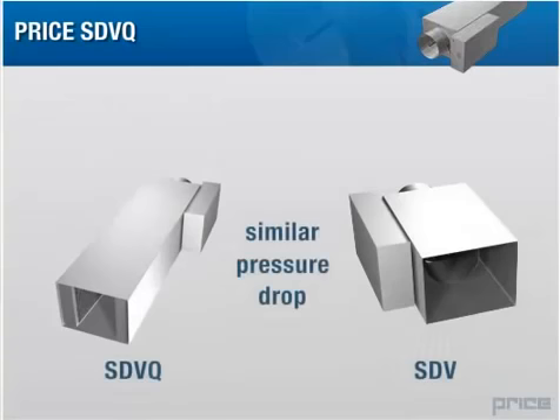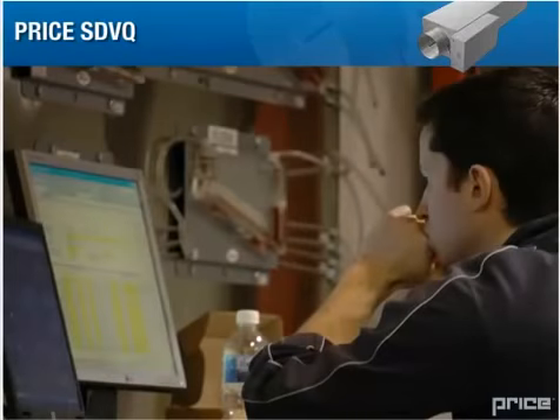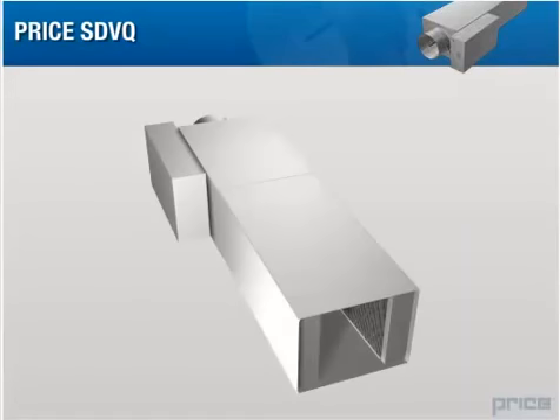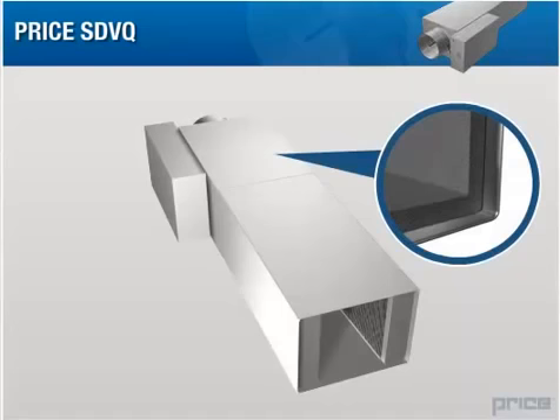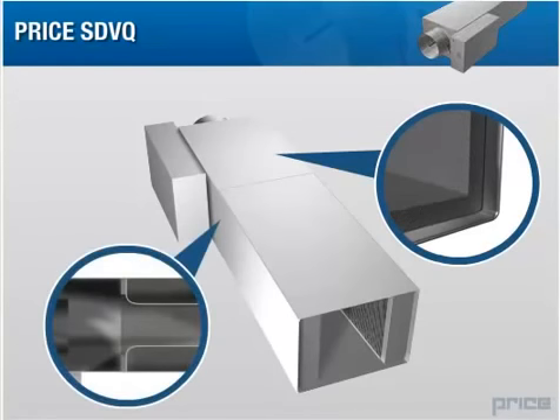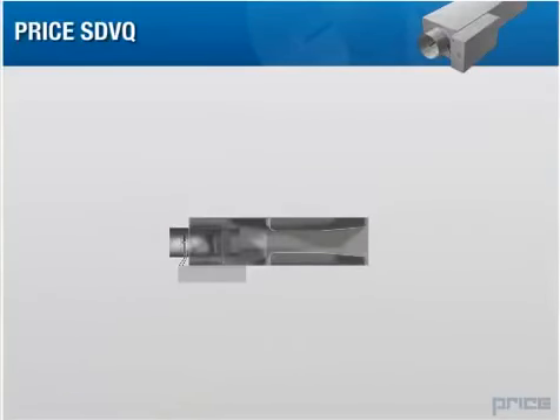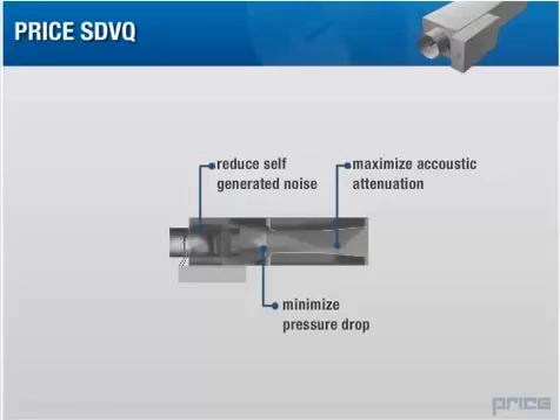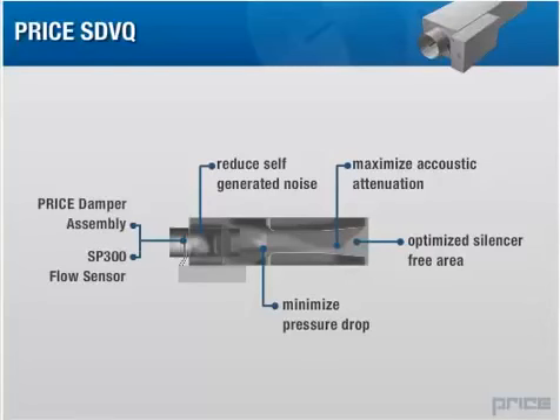These fully tested units with optimized geometry have similar pressure drops to that of standard SDV units. This allows the engineer to eliminate allowances for extra silencer pressure drops in the HVAC system. The VAV casing is lined with 1-inch insulation for optimum noise reduction and is designed to ensure an even velocity profile into the silencer section. The casing design and optimized silencer geometry reduce self-generated noise, minimize pressure drop, and maximize acoustic attenuation. The silencer-free area is optimized to match the terminal capacity, and the unit comes with the proven Price damper assembly with accurate SP300 flow sensor.